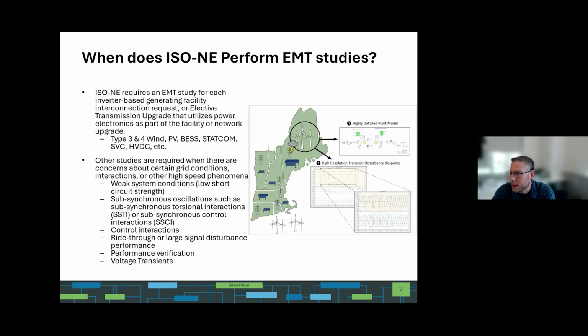Today I'm going to talk about EMT models, studies, and methodologies. So the first question is: when should you run an EMT study? For us, we run an EMT study for any interconnection request coming in. We'll run them specifically for power electronic switching type resources — inverter-based resources, StatComs, batteries, VSC, HVDC — anything with fast switching that can't really be captured in PSSE or positive sequence space.